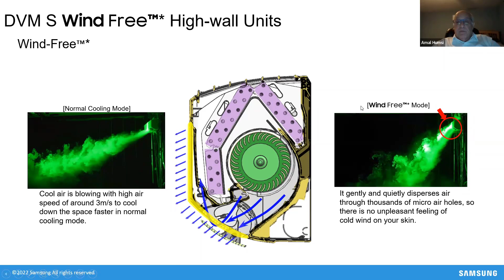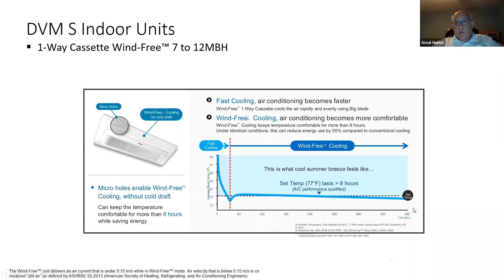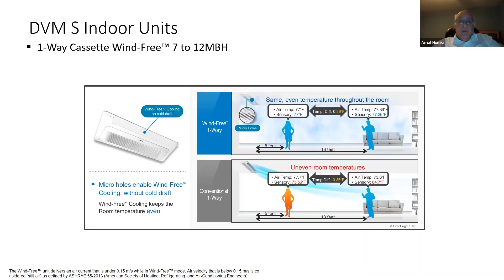And that's a typical example on like a one-way cassette. So basically the unit starts regularly until it reaches the set point, and then it will maintain the set point. But if you compare a traditional unit with a wind-free unit, so this is a conventional unit with 2 people at 5 feet and at 13 feet. And there is almost a delta of 10 degrees between what those 2 different people are feeling. While if you have a wind-free, because the air is mixing through convection in the space, there is only a 0.36 degrees difference between somebody standing at 5 feet and somebody standing at 13 feet. So you are providing comfort to your customers.